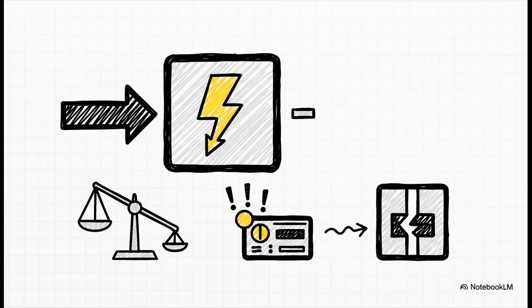Okay, but now let's change the scene. What if there's a problem inside the transformer, a short between the windings? All of a sudden, current is gushing in, but it's not all making it out. That imbalance, that's the smoking gun. That's the broken laser beam. The relay sees that difference and trips the breakers in a fraction of a second to isolate the transformer and prevent it from tearing itself apart.